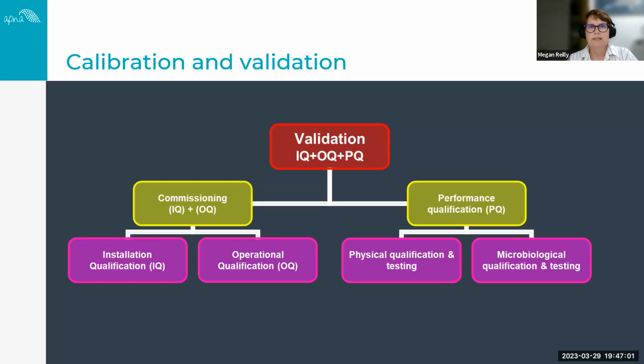And coming towards the end is our calibration and validation. A critical part, we need to know that our equipment is working. Our washer disinfectors require validation and our sterilizers require validation. Validation consists of commissioning, so at the time of acquiring the sterilizer, and also when performance qualification is performed. What it's doing is evaluating the reliability of the reprocessing process, whether that's the washer disinfector or the sterilizer.